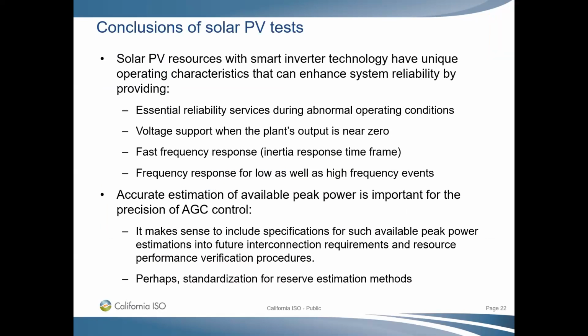Yeah, we've got a question. When the solar plant got a dispatch signal to reduce, did the excess power go to storage, or were PVs just taken offline? That's a good question. Currently, the big PV plants that we have, almost 14,000 megawatts of PV, have no storage. The newer plants coming in now have storage. So to answer your question, when we curtail, you just lose that energy. Gotcha.